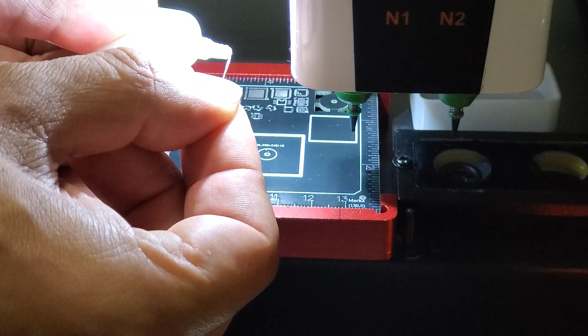For this reason, I use a little bit of grease, so when the disc is placed on the board, it will stick till the next lift up. But pay attention, too much grease will result in the disc not being able to be lifted up. In this case, the procedure will be stopped with the message, "Target not found."